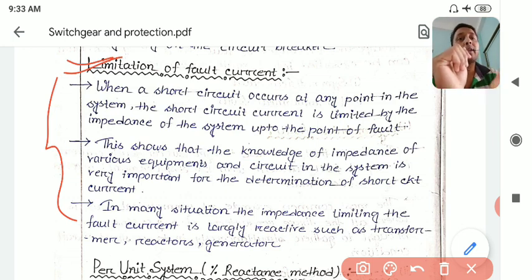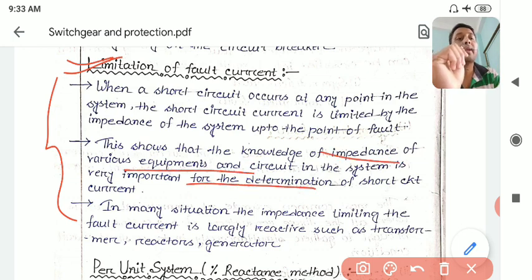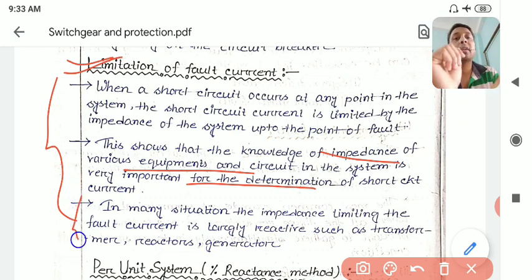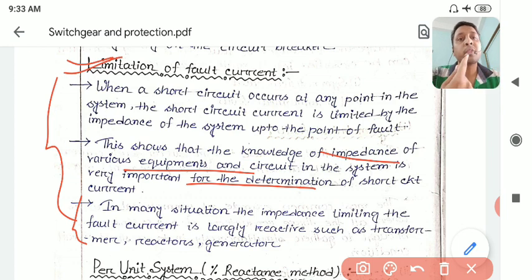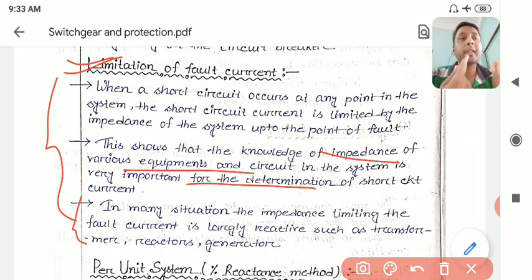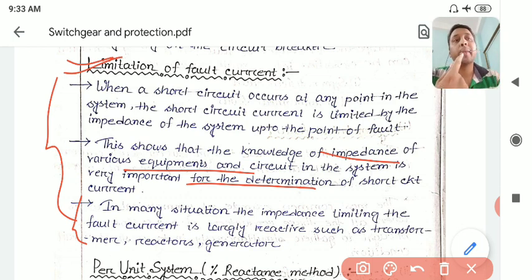In order to prevent high fault current, you first need to know the impedance of each and every equipment, as seen in the per-unit diagram or short circuit analysis. Once you know the short circuit current, you can limit it. If the fault current is very high, switch gear equipment like circuit breakers and relays used to trip during a fault will be overstressed. To reduce the burden on the circuit breaker and other equipment and to make the system run smoothly, we have to limit the fault current.